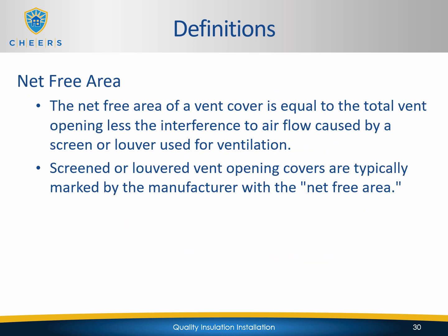Net-free area. The net-free area of a vent cover is equal to the total vent opening less the interference to airflow caused by the screen or louver used for ventilation. Screen or louver vent opening covers are typically marked by the manufacturer with the net-free area. So anytime you're buying a louver or a vent of some type, the actual product specifications will tell you what the net-free area for that particular vent is. It'll be specified by the manufacturer.